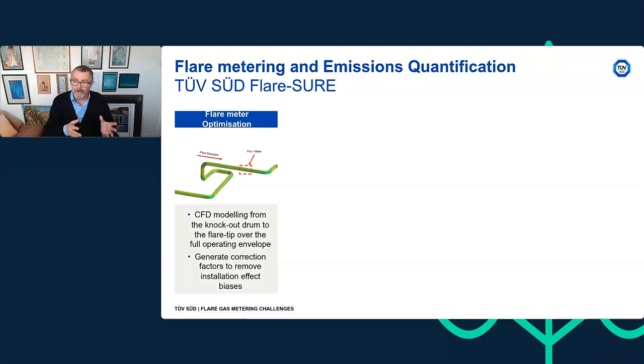There are four parts to FlareSure. We can and have used CFD modelling all the way from the knockout drum to the flare tip, over the full expected or historical operating range of the meter, to model its performance and any installation effects. That allows us to generate correction factors, which can be significant - 5, 10, 15, 20, 25% - based on the customer's pipework, process conditions and fluids, to remove installation effect biases.